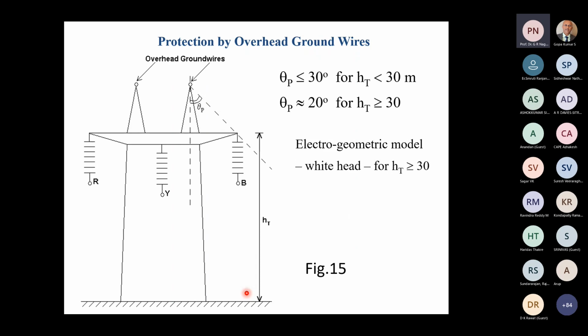Now, suppose you have very broad lines. For example, if you think of a 400 kV line or 800 kV line or 1200 kV line, the conductors cannot be one above the other. They are horizontal like this. The tower will be roughly of this shape. So we have to provide two overhead ground wires. Now here we use the geometric method: for height less than 30 meters, 30 degrees. For height greater than 30 meters, reduce this protective angle to 20 degrees.